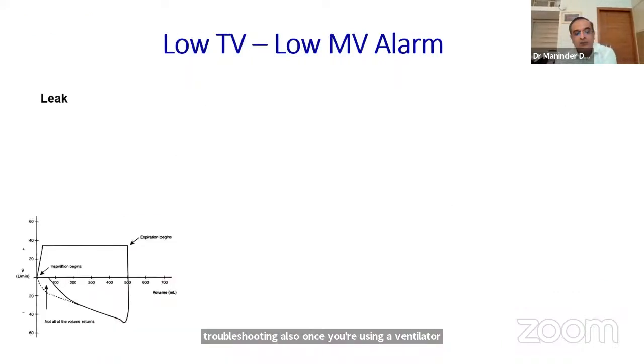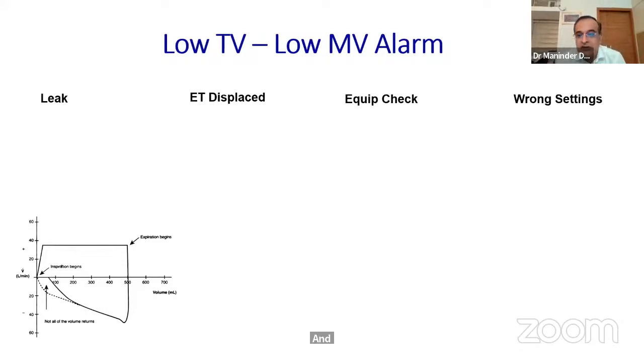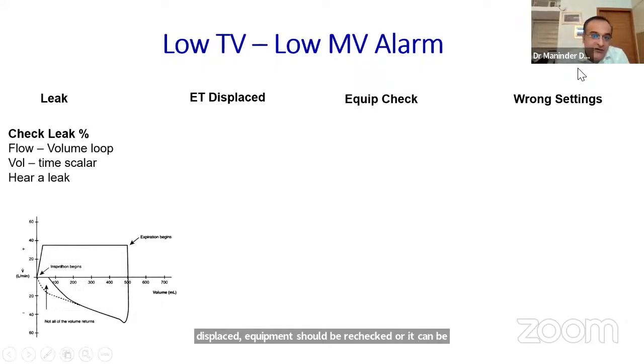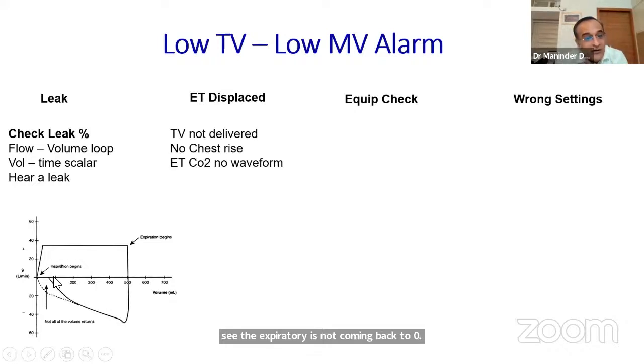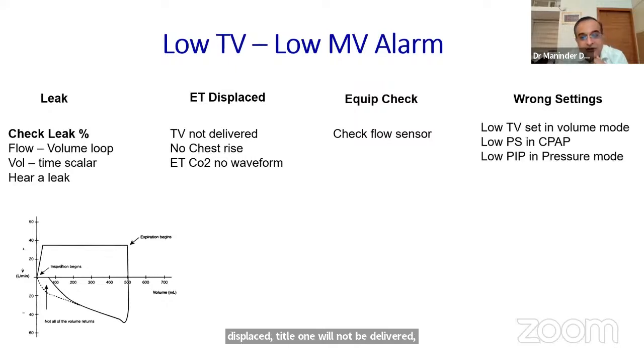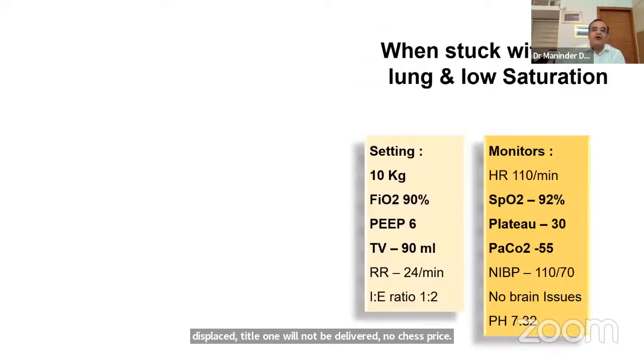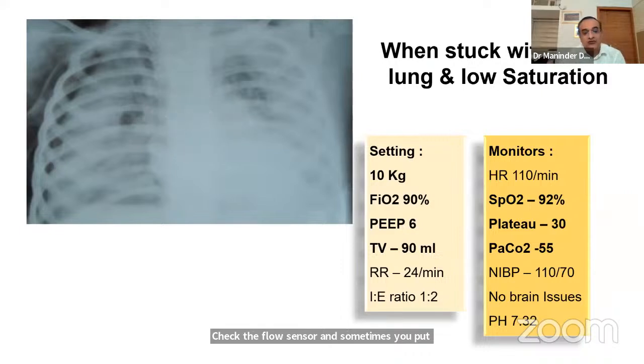Low tidal volume can be either a leak, ET displaced, equipment issue that should be rechecked, or wrong alarm settings. If it's a leak, check for the leak in the scalars - you can see the expiratory is not coming back to zero, it should come here but it's finishing below that. If ET is displaced, tidal volume will not be delivered, no chest rise. Check the flow sensor, and sometimes settings are wrong. This is an X-ray which we commonly get stuck with.